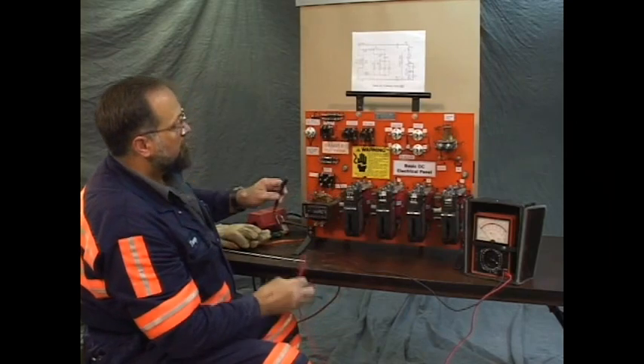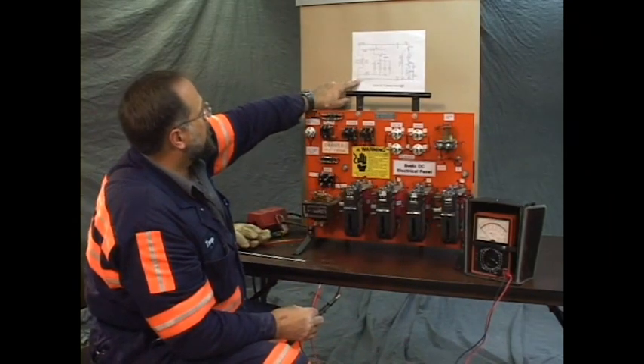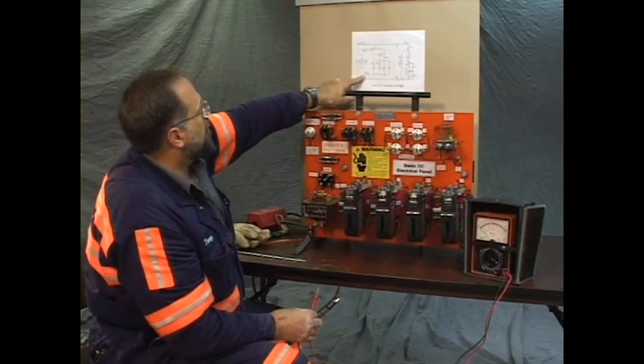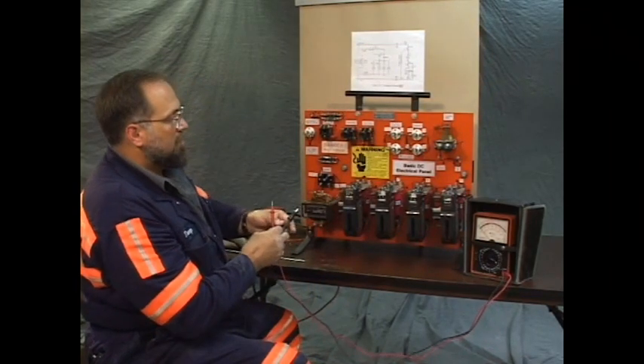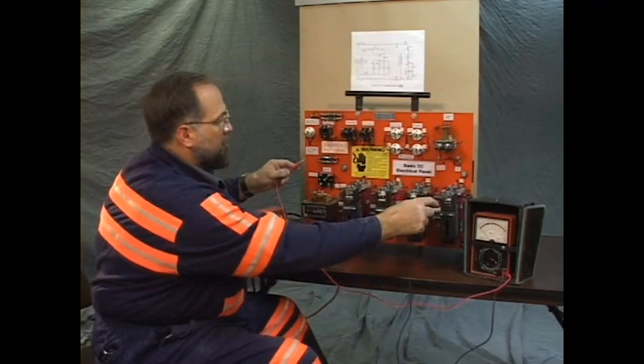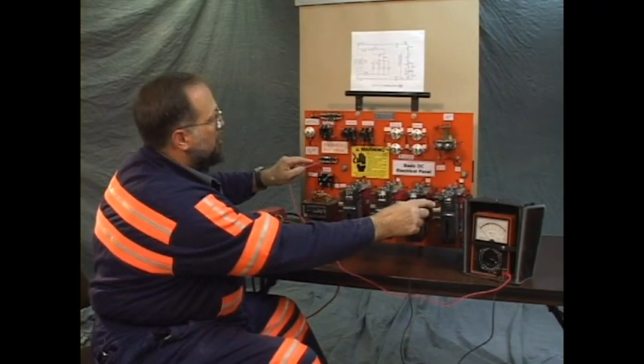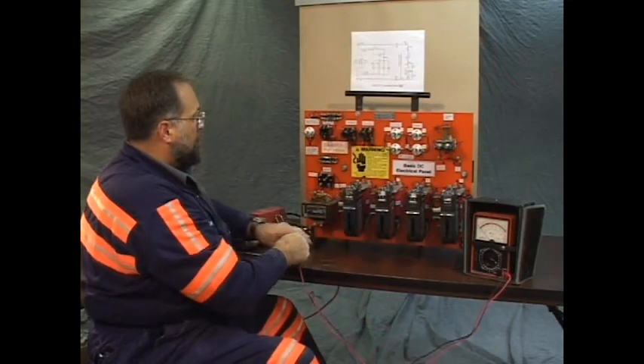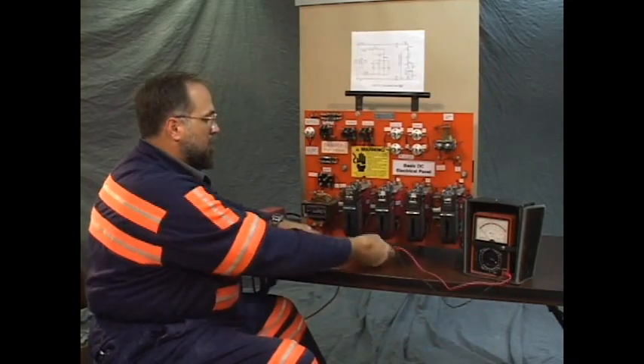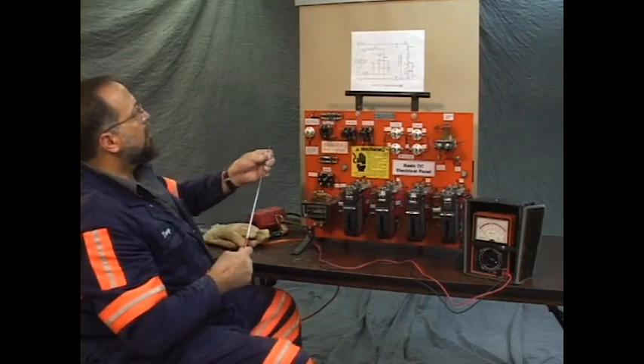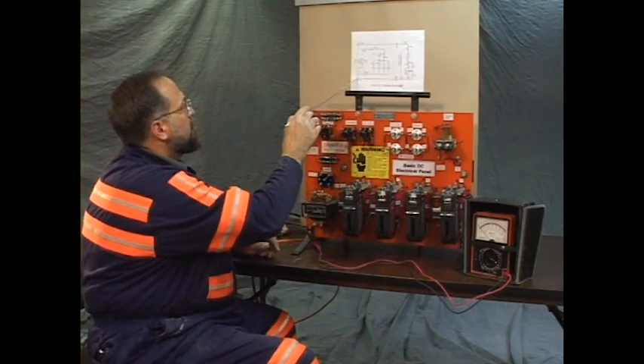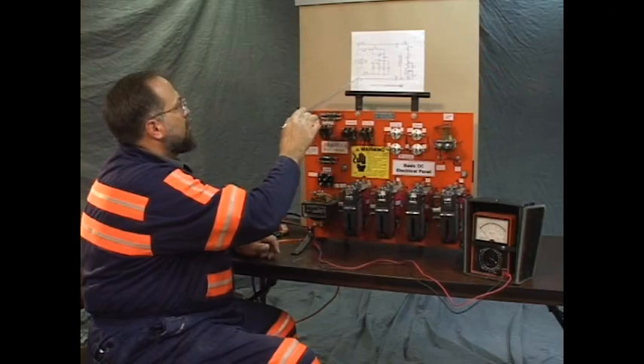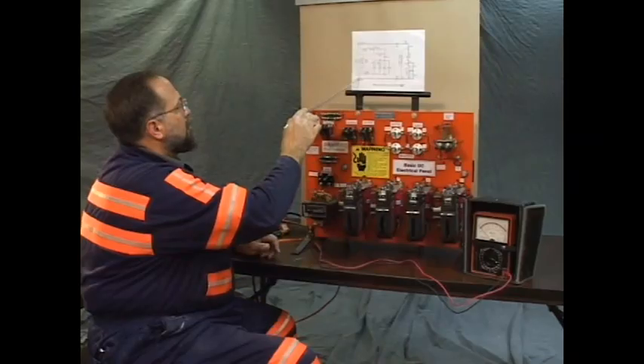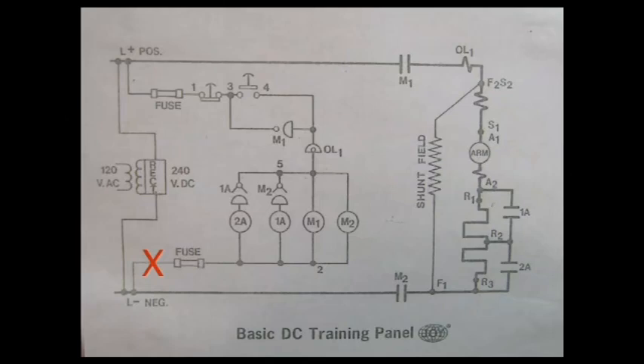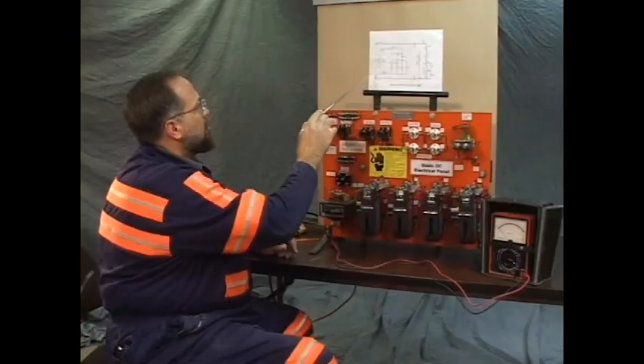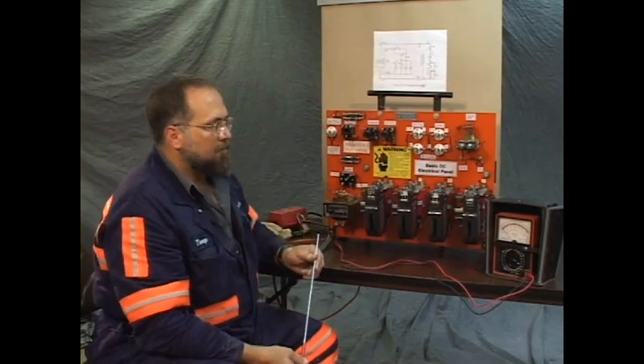To further isolate that, the wire shown on the drawing from the top front of M2 to the line side of the fuse, I'm going to move my probe to that point. No circuit. There you have it. This problem, we have an open wire from the top front of M2, this point here. The wire between the top front of M2 contactor to the line side of the negative fuse is open, right there. And that's that.